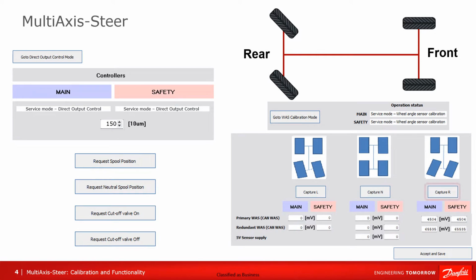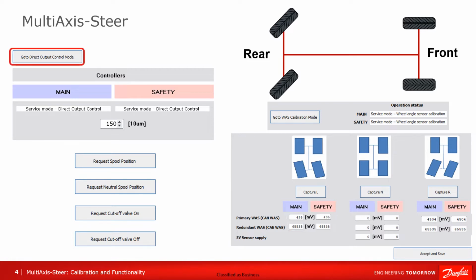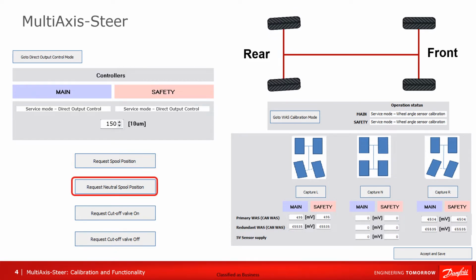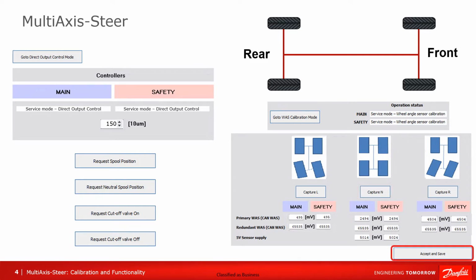Then press Capture L or R to capture the values for the left or right side. This should be repeated for both sides. The center position is found by entering direct output control mode and requesting a spool position just outside the deadband, and then requesting a neutral spool position when the wheels are in neutral. Then go to WAS calibration mode and capture the neutral position. After capturing all of the values in the WAS calibration page, press Accept and Save. It is important to only press the Accept and Save button once all the values are captured.